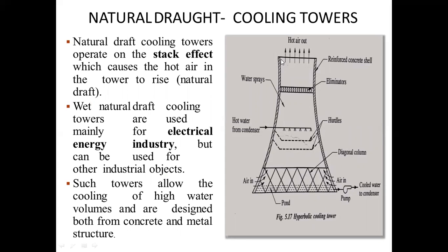The shape of a natural draft cooling tower is hyperbolic. Here you can see we are using some baffles or eliminators, which help us to reduce the loss of water due to evaporation. The height of this tower is very large. Hot water from the condenser is supplied and sprayed here. Now the air which enters from the bottom side comes in contact with this hot water and moves upward. There are eliminators which help to reduce the water losses.